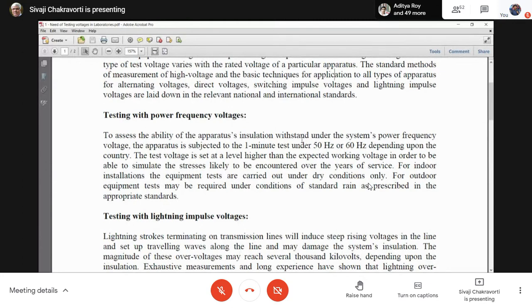So what we do, we generate power frequency voltage within our lab, but not at the rated operating voltage, but at an elevated voltage. And we apply that high voltage to the equipment and we try to see whether that equipment is able to withstand or not. If it is able to withstand, it means the quality of the equipment is good. If it cannot withstand, then it is bad quality. So the customer will say that, no, I will not take it.